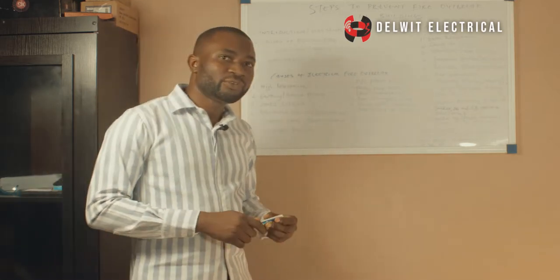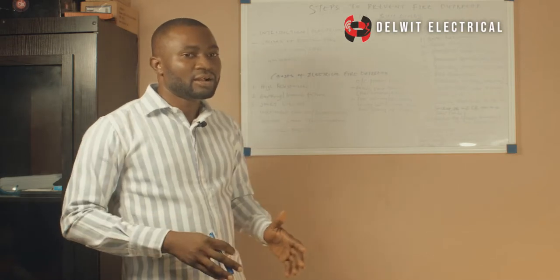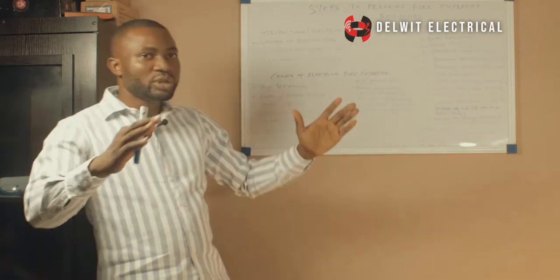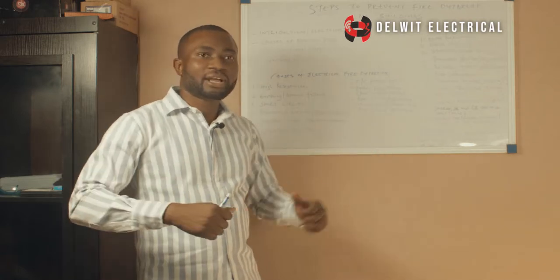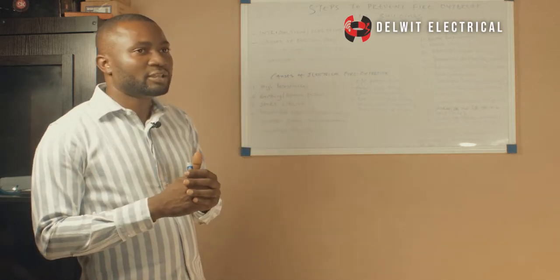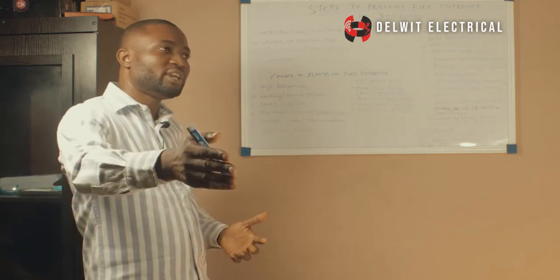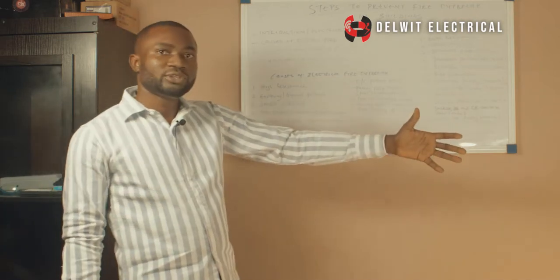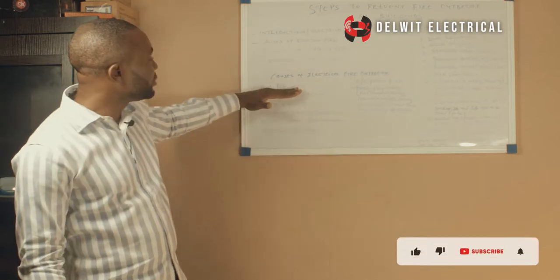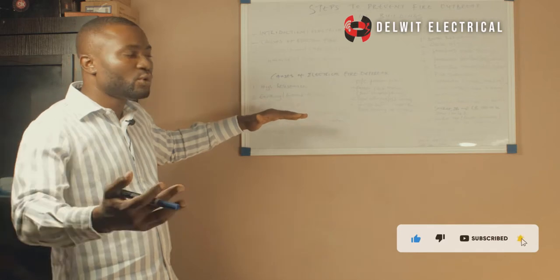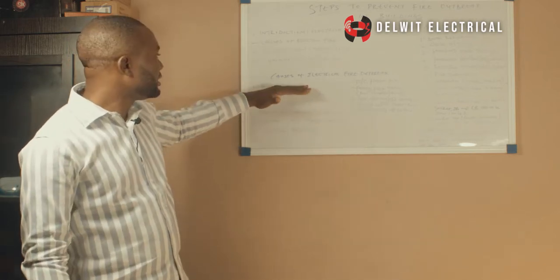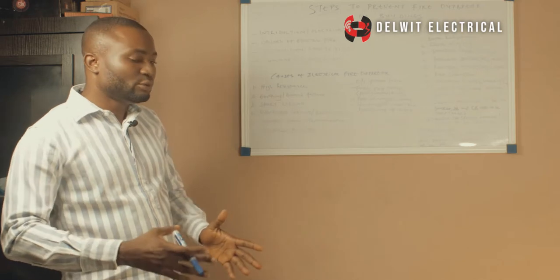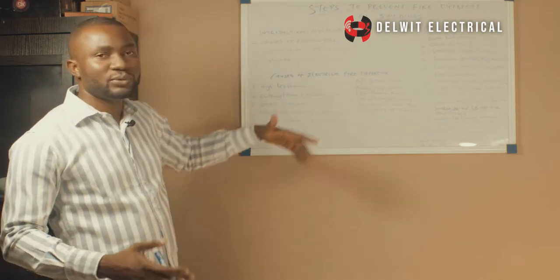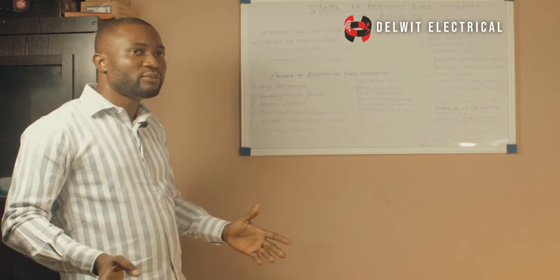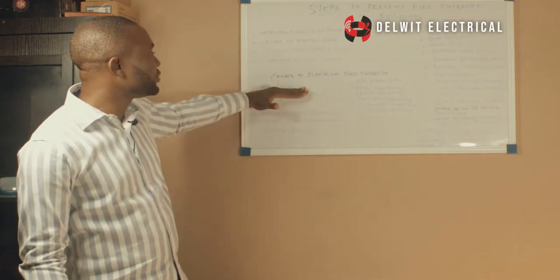Like I said in the previous video on fire disaster, I talked about high resistance, having two entrances, where at one you have a big bodyguard and at the second one you have a slim bodyguard. Most people will prefer to go through the entrance that has the slim bodyguard than the one that has the big bodyguard. The same thing happens with high resistance. Whenever there is a fault current, the fault current tends to flow towards the area with low resistance. In that case, if your earth does not have a low resistance, definitely you will discover that current would flow to your equipment. And what are the major causes of high resistance?